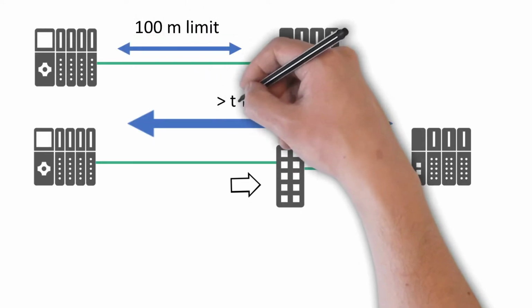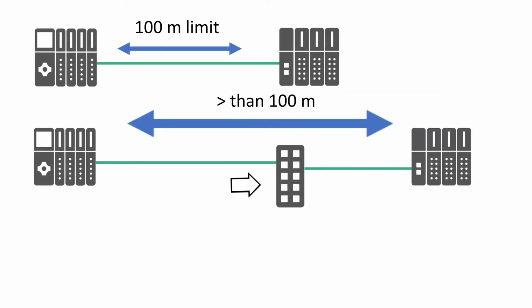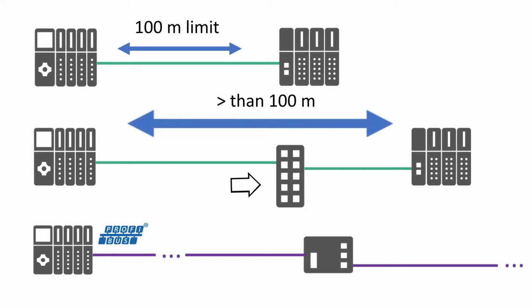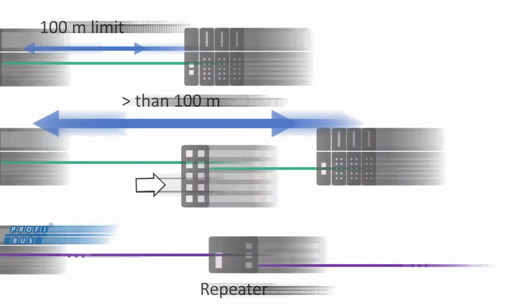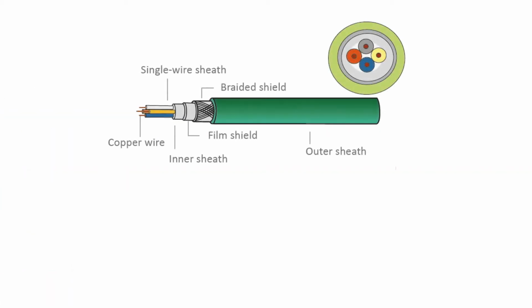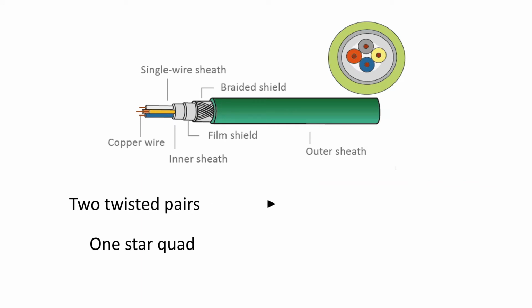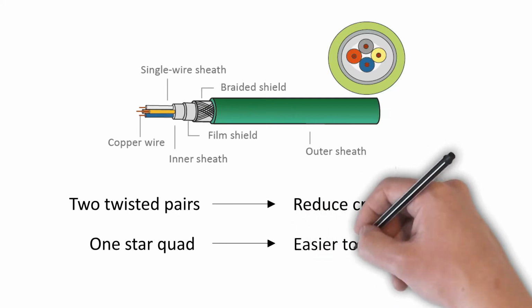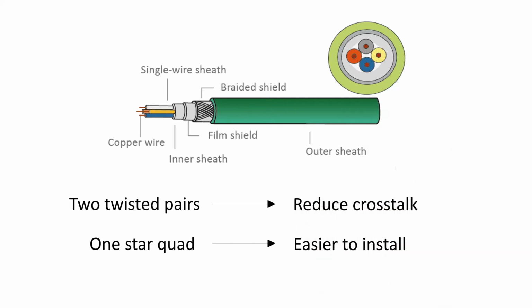In order to go further distances than the 100 meter limit, you have to install a node, like for example a switch, every 100 meters. It's similar to cable segments as a limiting factor in traditional field buses. For example, in Profibus networks, you would implement Profibus repeaters between segments to go longer distances. The 4-wire cable can either be realized as 2 twisted pairs or as 1 star quad. On the one hand, twisted pairs can help reduce crosstalk between the wires, but on the other hand, star quad cables are easier to install and therefore more common.